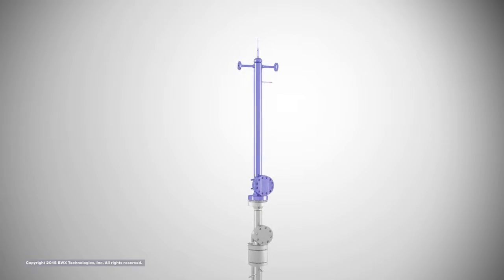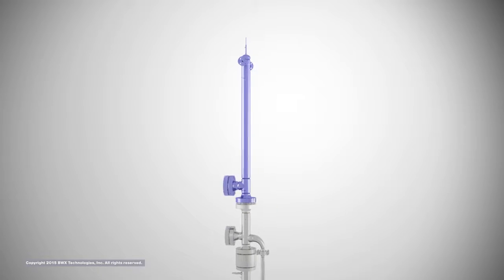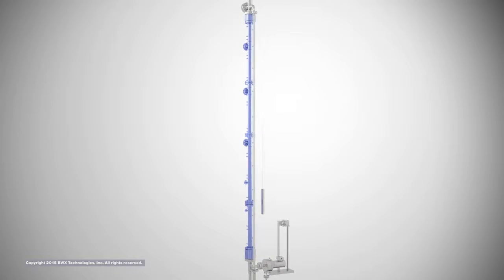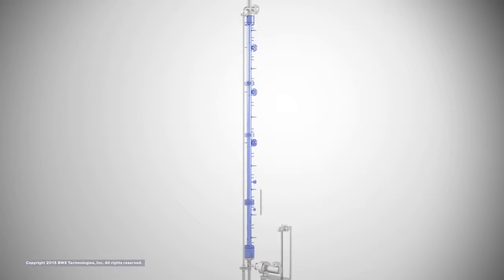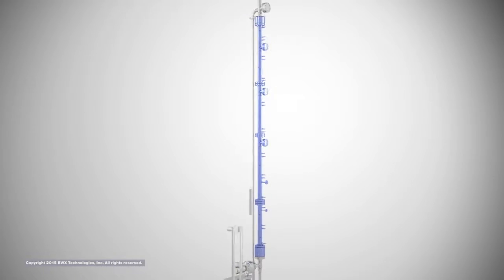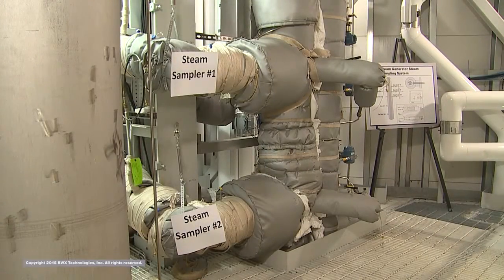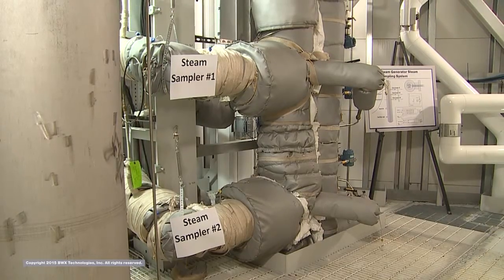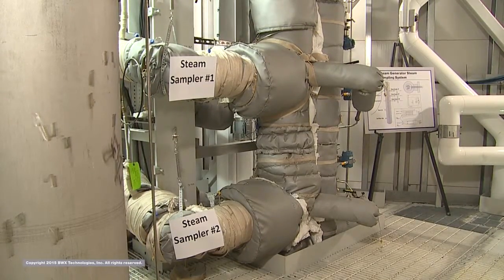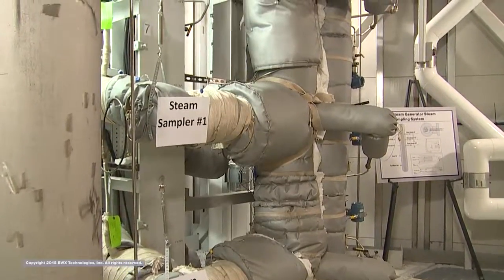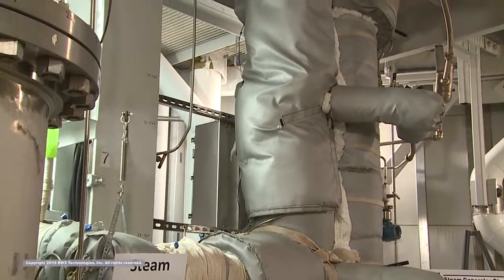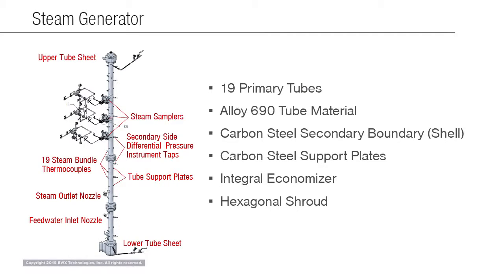The once-through steam generator is a straight tube design with counterflow. It produces superheated steam, exhibits four unique heat transfer domains, and features steam samplers at three elevations in the steam bundle to measure the moisture content of the steam during operational conditions and during variations in steam generator test conditions designed to investigate heat transfer.